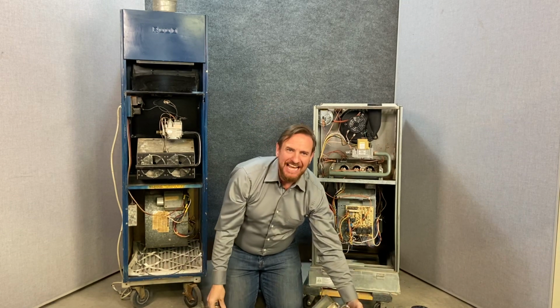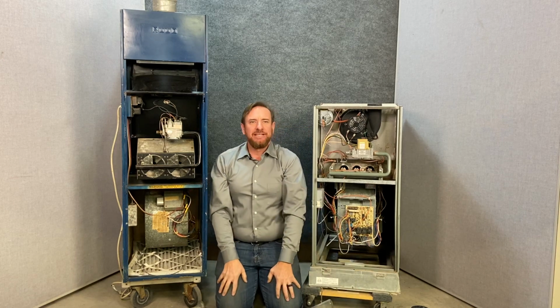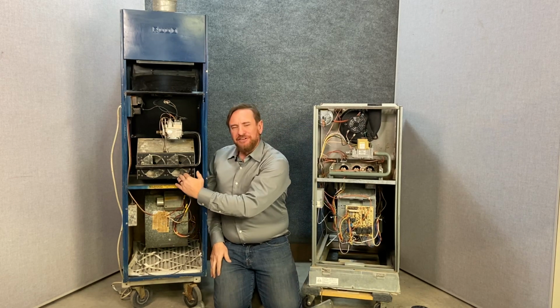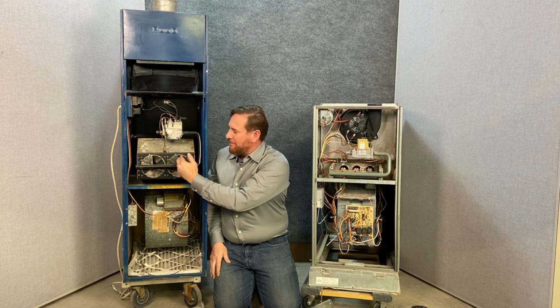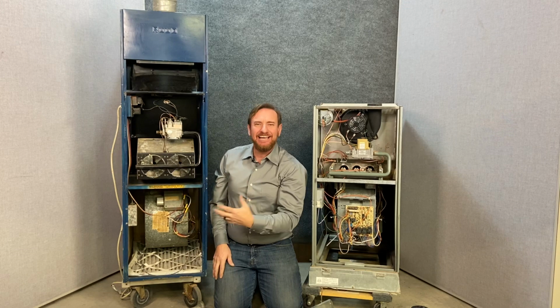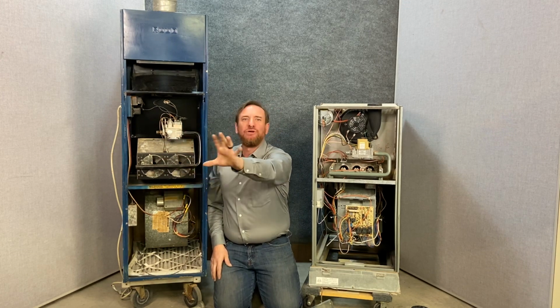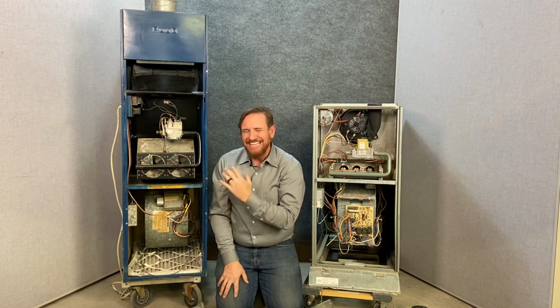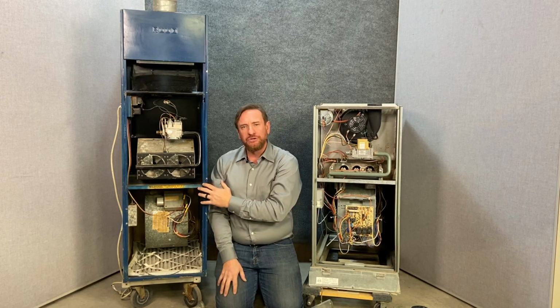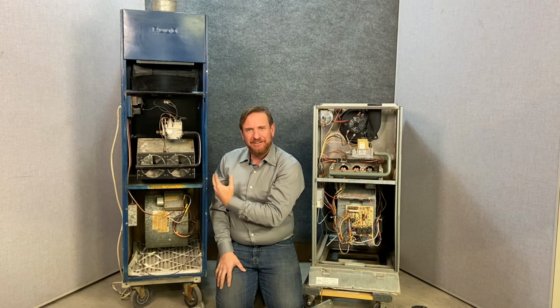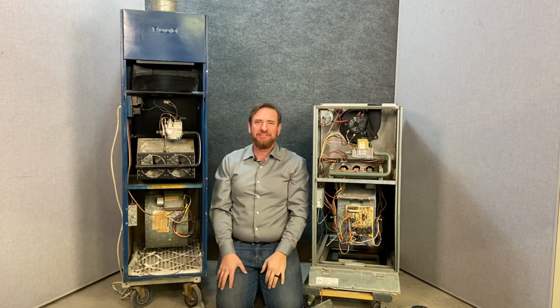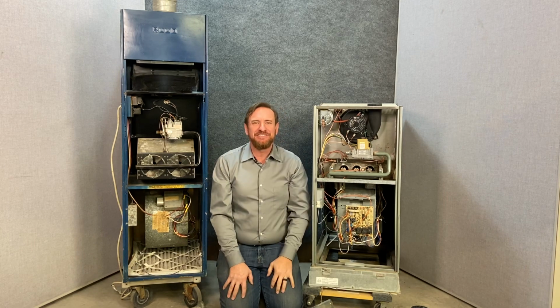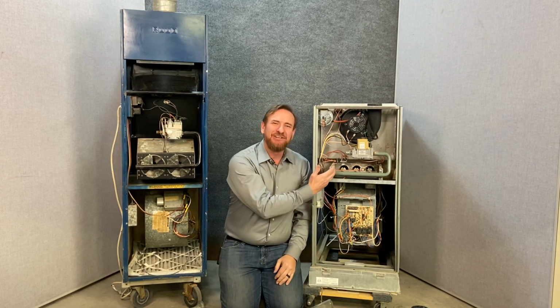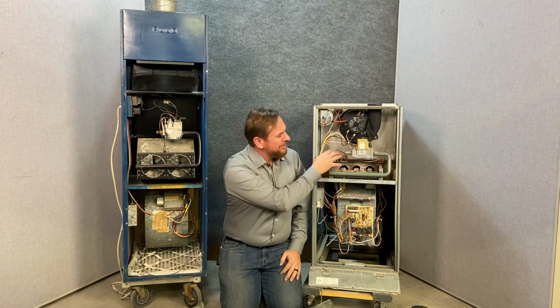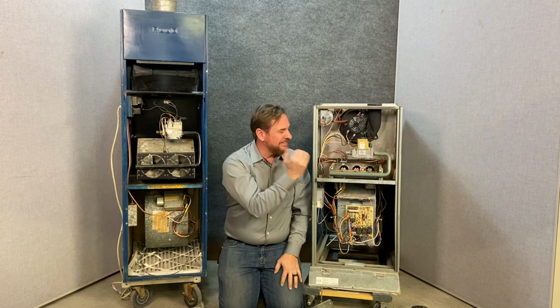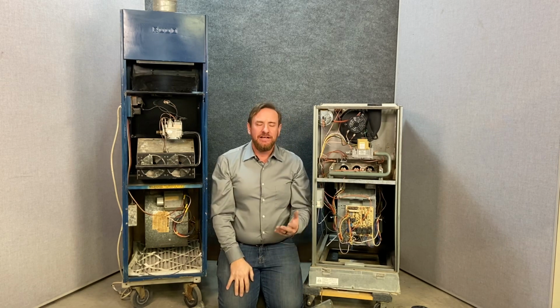These old furnaces didn't have anything like that. The only thing that they had was their standing pilot light. Sometimes you would see on these furnaces, this one would light right here, but the other one wouldn't light. And when it would finally light, all the gas would build up, and you'd have a flame roll out of the system. So I always tell my students, on any gas furnace, whether it's a modern one or an older one, you want to make sure you're standing to the side of that furnace, in case that flame rolls out, it's not going to hit you in the face. There have been technicians before that lost their mustache, messed up their beards because they were standing right in front of that furnace. So you stand to the side, so if that flame does come out, it's not going to hit you. Once it lights up, you can then look in there and make sure everything's working correctly.